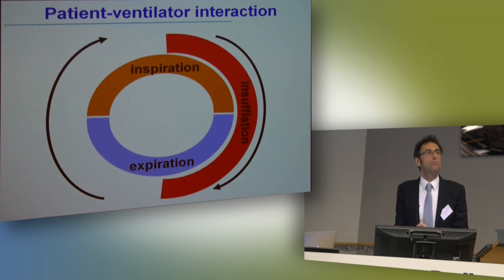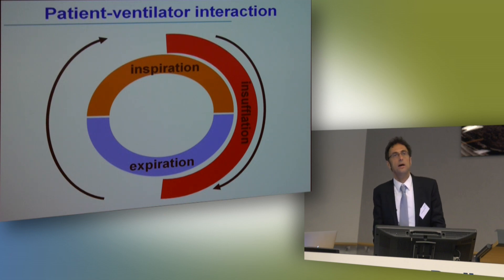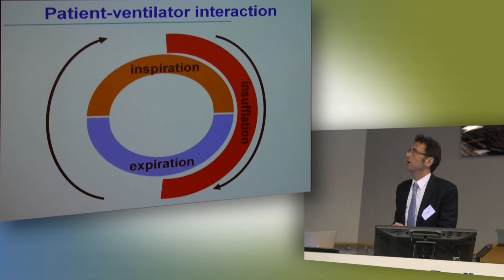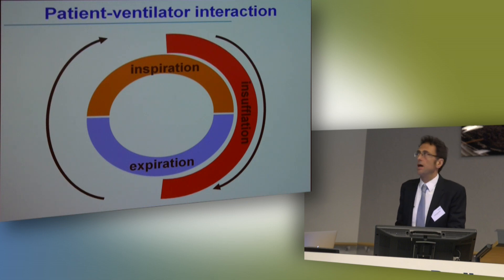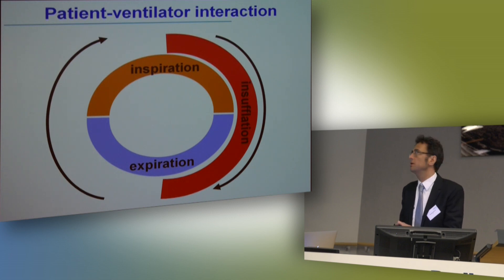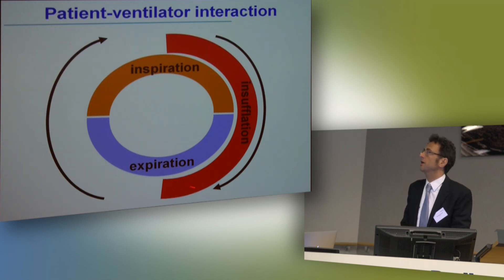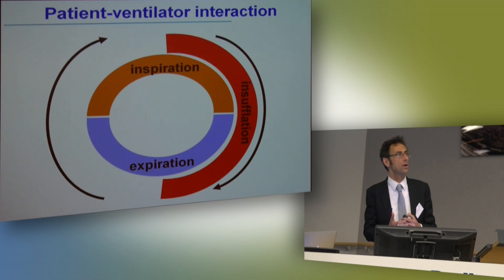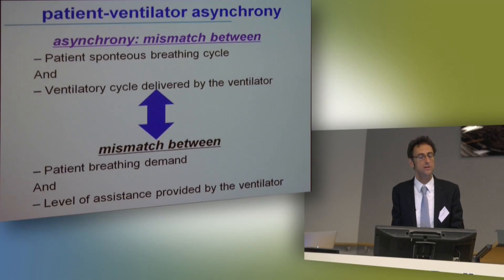The problem starts when those two actors are not synchronous — when the insufflation of the ventilator, for example, starts after the beginning of the patient's inspiration and then continues during the patient's expiration. Things can turn chaotic and they could be completely desynchronous. We can define asynchrony as a mismatch between the patient's spontaneous breathing cycle and the ventilatory cycle delivered by the ventilator.